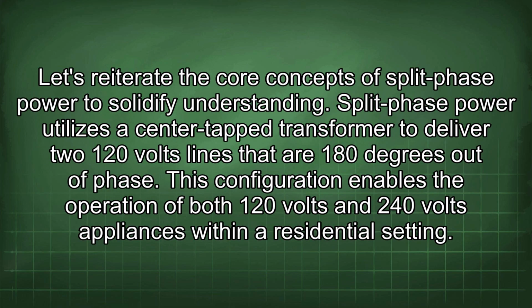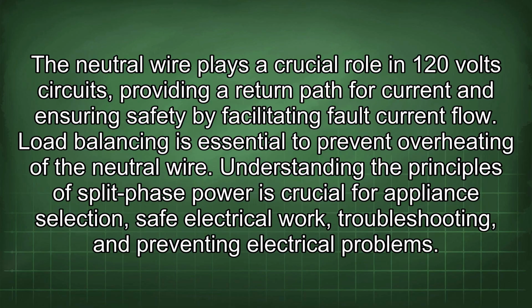Let's reiterate the core concepts of split-phase power to solidify understanding. Split-phase power utilizes a center-tap transformer to deliver two 120 volt lines that are 180 degrees out of phase. This configuration enables the operation of both 120 volt and 240 volt appliances within a residential setting. The neutral wire plays a crucial role in 120 volt circuits, providing a return path for current and ensuring safety by facilitating fault current flow.